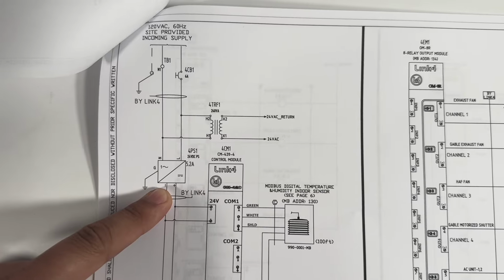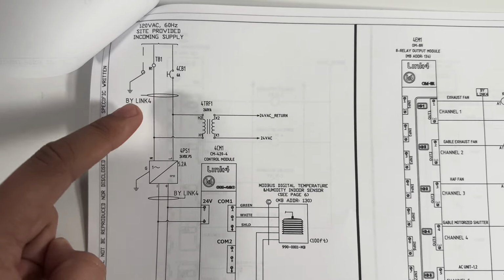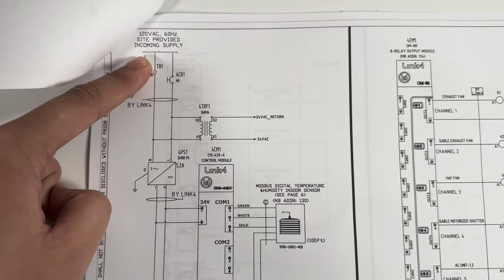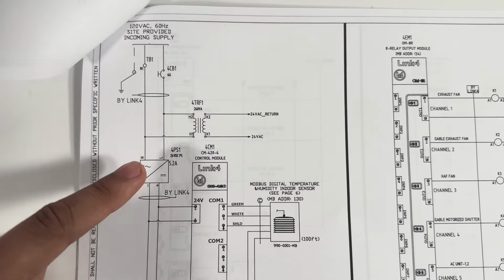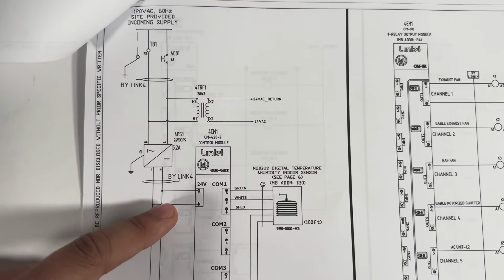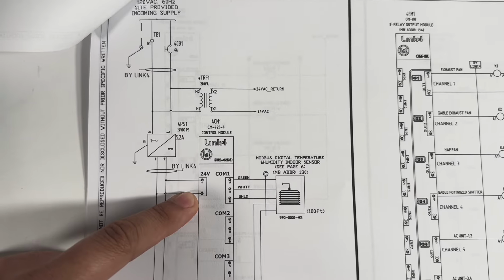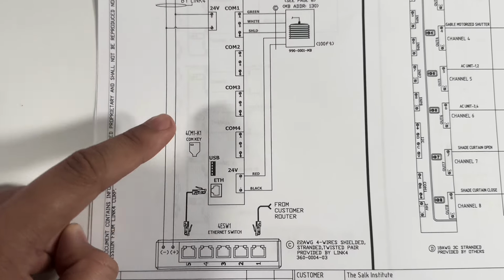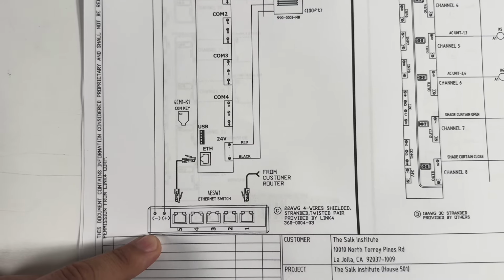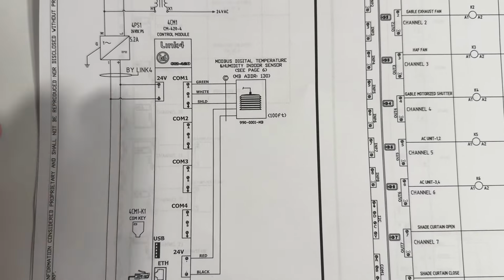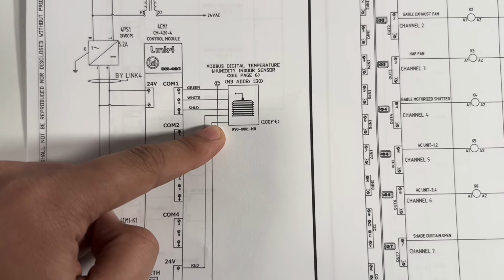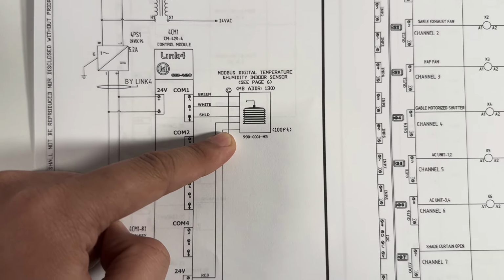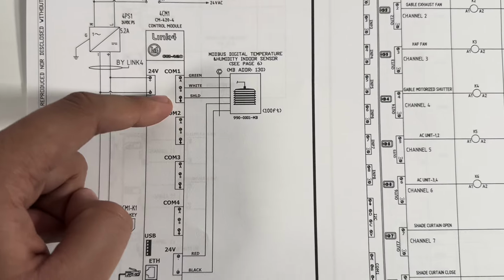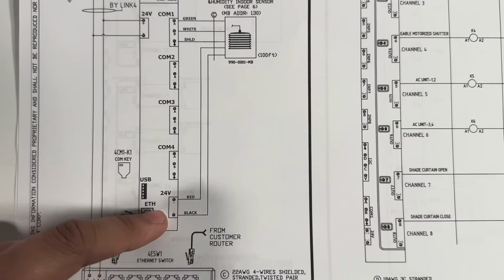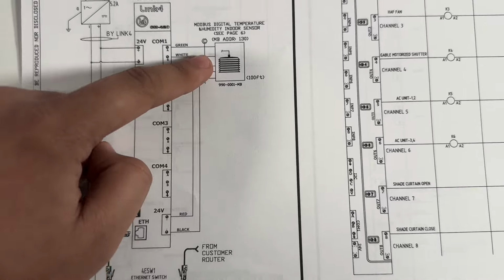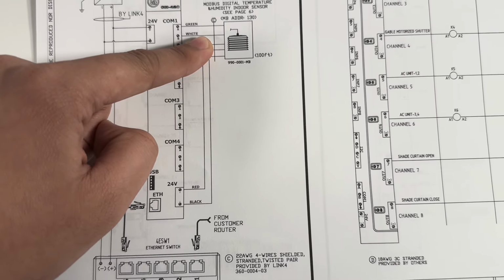Here we can see our 24 volt DC power supply. It is getting 120 volts AC power coming from the wall. This power supply is then converting it to 24 volts DC to be used by the Pearl controller, as well as our Ethernet switch. Over here we can see the DTH. The DTH is connected to the Pearl on COM 1 with 3 communication wires and 2 power wires. It uses a 22 gauge 4 wire shielded stranded twisted pair.